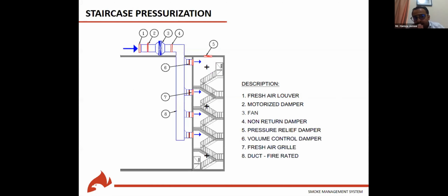In another system, another application is the staircase pressurization. As we said before, there is an application of fresh air applying a positive pressure in the stairwell, preventing smoke from entering this area. As you can see, the components of the system are fire rated duct, a motorized fire damper, fresh air grille, fans, and other fresh air louvers. And all are controlled using a well-defined sequence of operation in conjunction with the fire alarm and the fire safety scenario in the building.